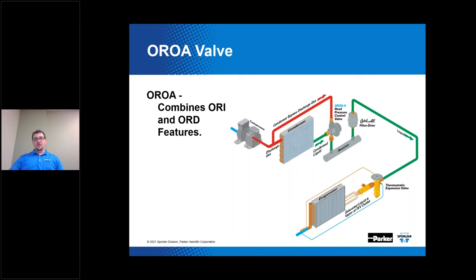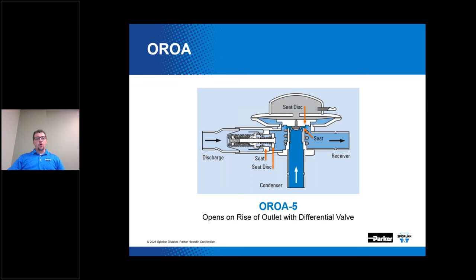Installation requires three connections — one less than the separate ORI and ORD. This valve is non-adjustable, available with one of three standard pressure settings: 100, 180, and 210 PSIG, with other pressure settings available if needed. It also has an ORD built into its mechanism on the compressor discharge side of the valve.